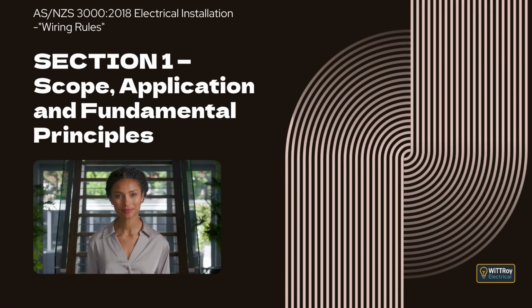Clause 1.5.5.4 explains that one way to protect people from dangerous voltages is to use Class 2 equipment, or equipment with equivalent insulation. This simply means the equipment has double insulation, or reinforced insulation, so even if one layer fails, another layer still keeps you safe. Sometimes total insulation is built into switchgear, and sometimes extra insulation is added during installation. The key idea is that strong insulation stops fault voltage from reaching metal parts a person can touch.